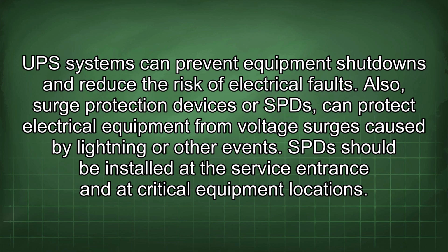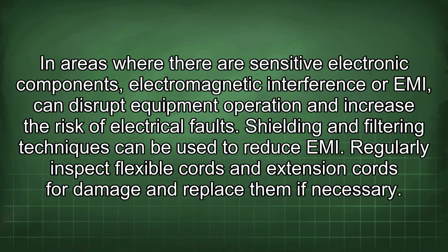Also, surge protection devices, or SPD, can protect electrical equipment from voltage surges caused by lightning or other events. SPD should be installed at the service entrance and at critical equipment locations. In areas where there are sensitive electronic components, electromagnetic interference, or EMI, can disrupt equipment operation and increase the risk of electrical faults. Shielding and filtering techniques can be used to reduce EMI.